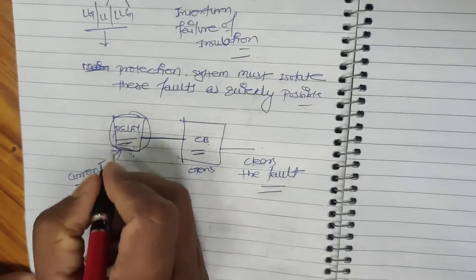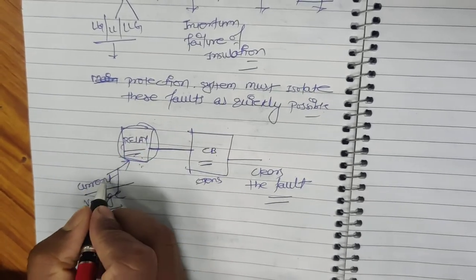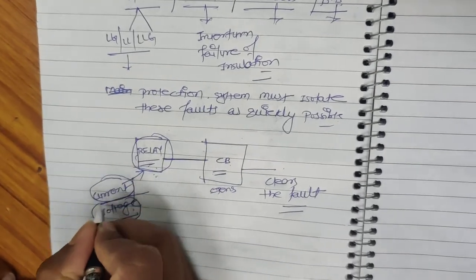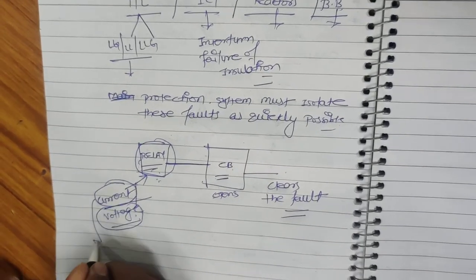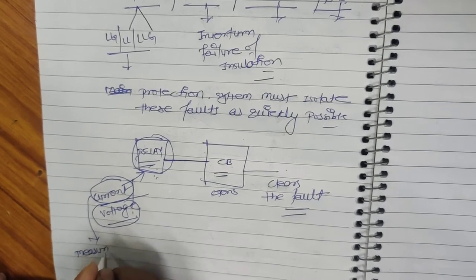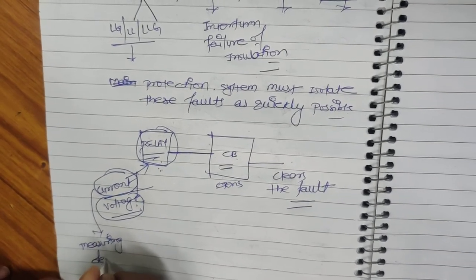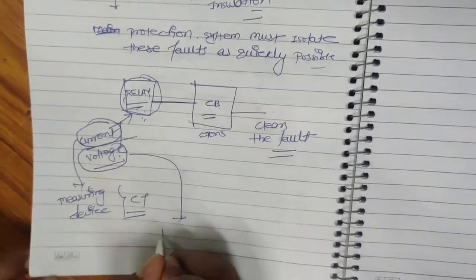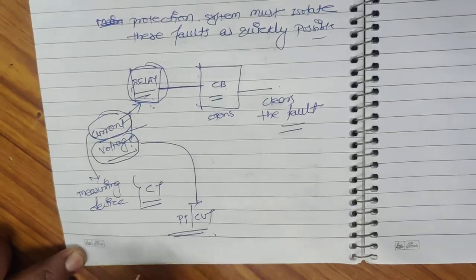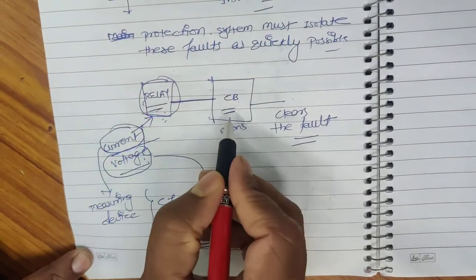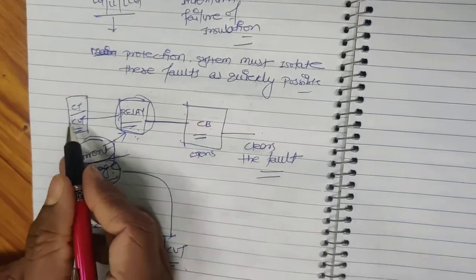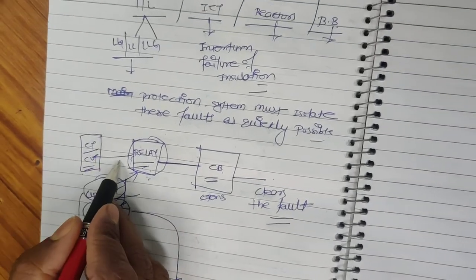For any algorithm, the relay must receive input signals from current and voltage. To send the current input signal, we need a measuring device — the CT (current transformer). For voltage, we use a PT or CVT (capacitive voltage transformer). So what comes before the relay is the CT and CVT. The CT and CVT continuously measure current and voltage and send these signals to the relay.